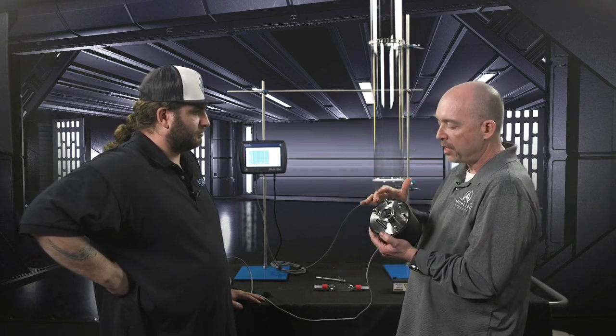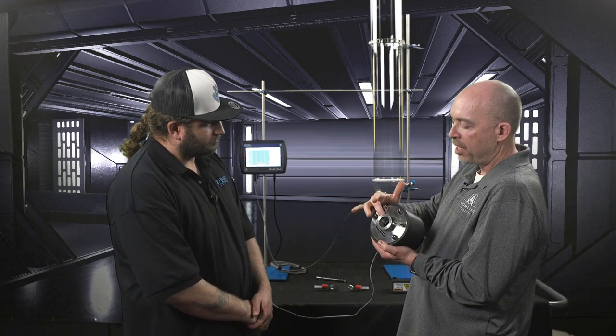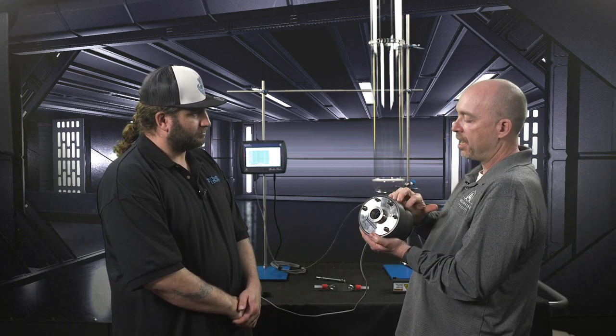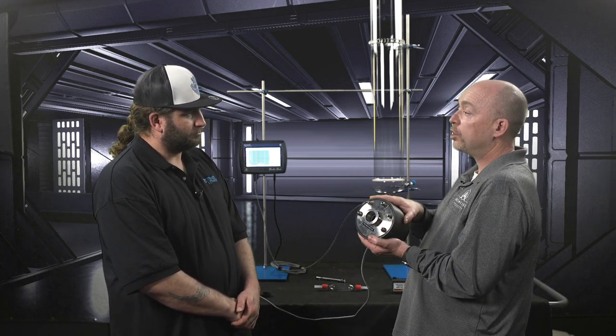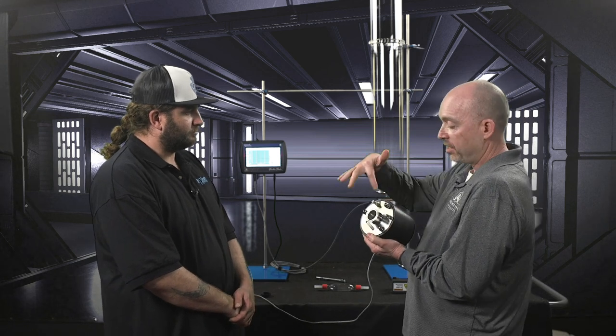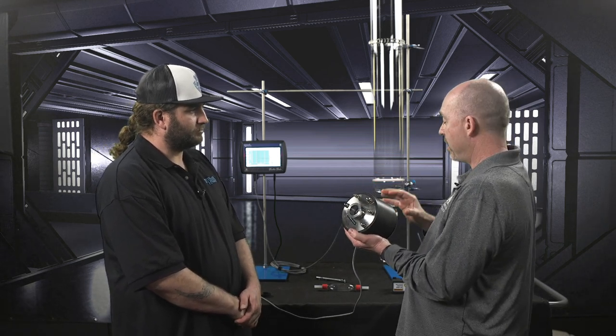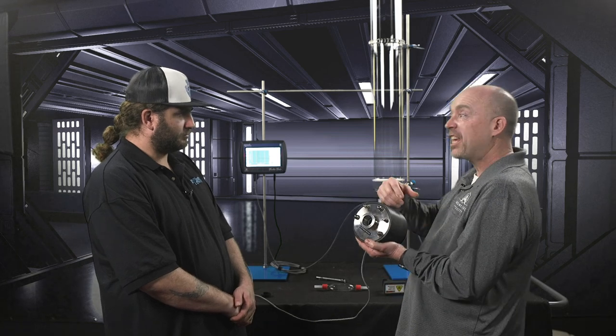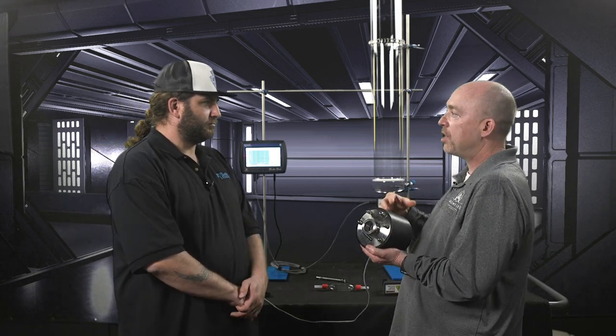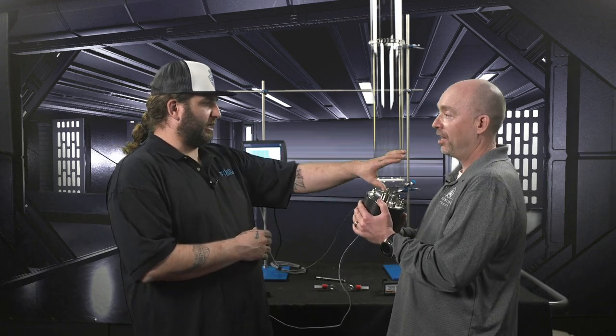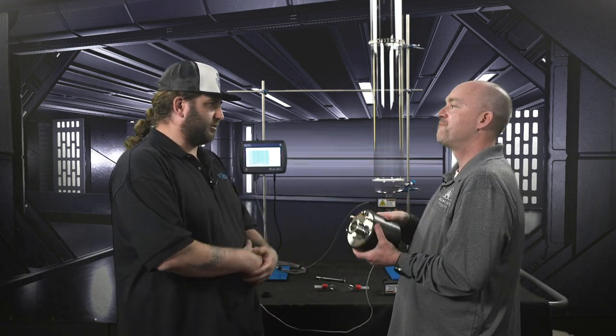So the next thing we had to tackle is how do we avoid ice? So then what we did is we created a device that actually had a shield around it. So literally it's a glass shield in here. Then we evacuate all the air out and we backfill with nitrogen. That way there's no water vapor there. So you can get as cold as you want and the ice will pile up in front or behind, but never in the sensor zone.